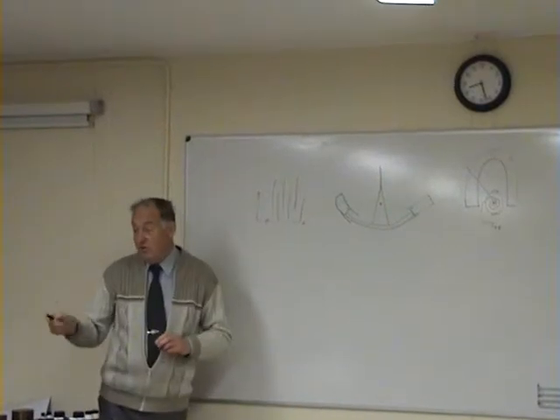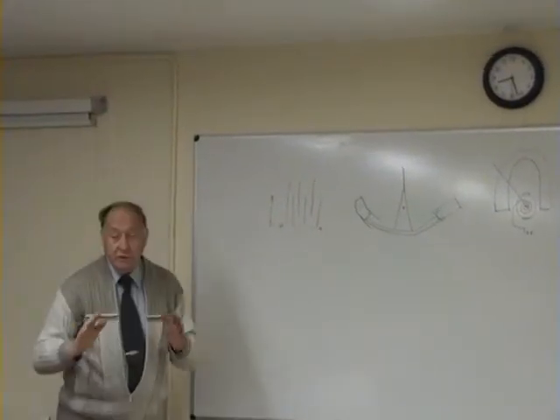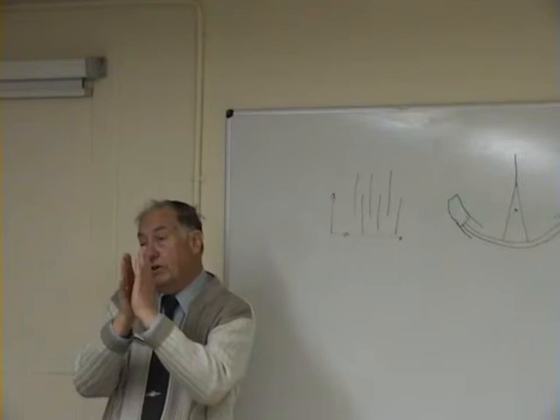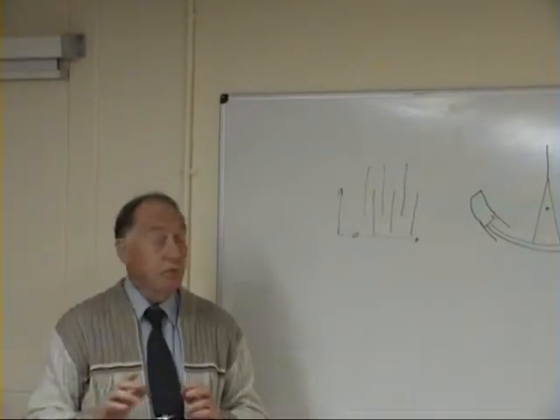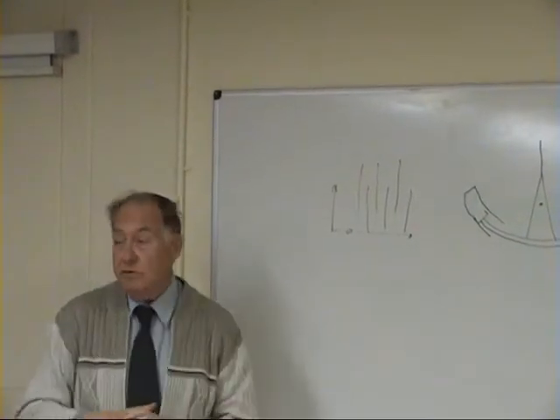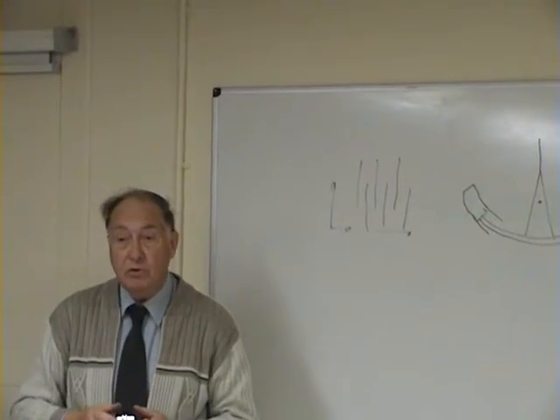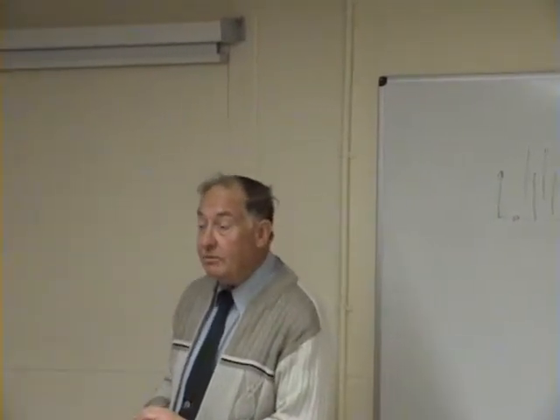It's a precision instrument, these. The lines of force will cause the moving plates to rotate and give a direct reading on the pointer as to what the voltage is. That's an electrostatic meter, reasonably common, but not really in amateur radio - that's more of an industrial type of instrument.